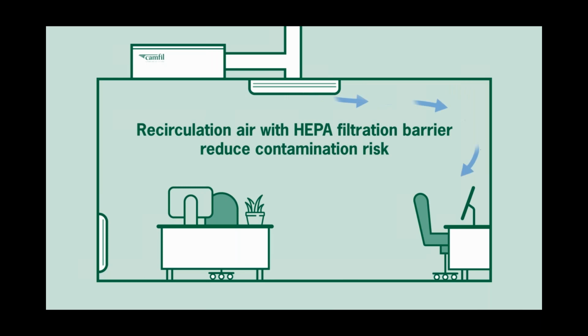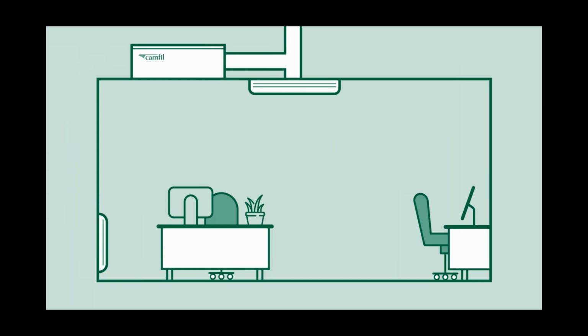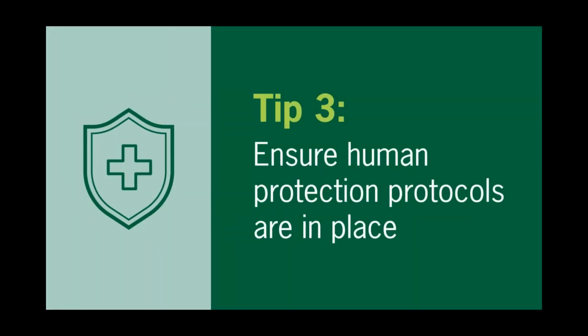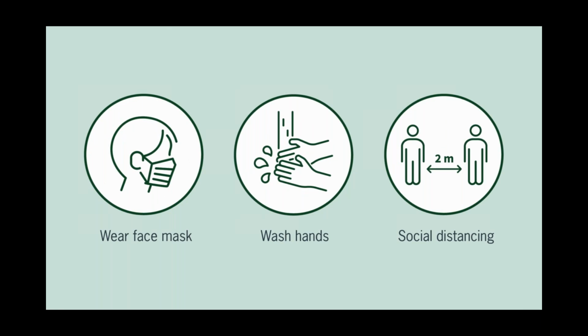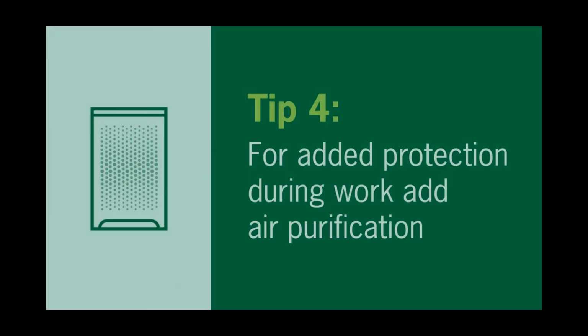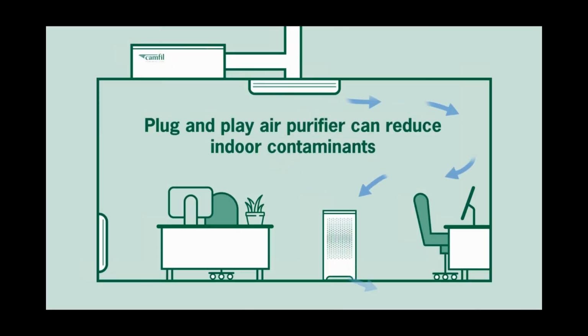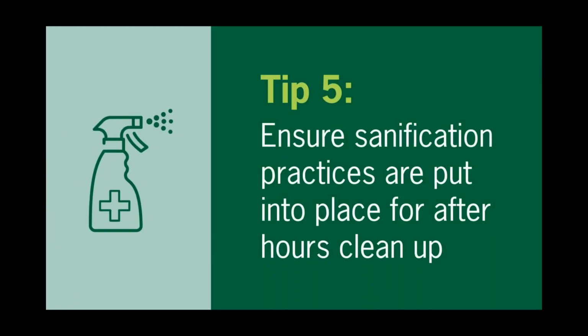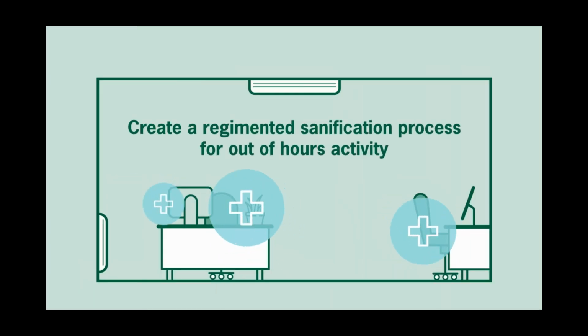And if recirculation is required, try and install a HEPA barrier somewhere. Whether that's up in the ductwork, that might mean adjusting some ductwork or adding an air cleaner in the ductwork. It typically might mean adding an air cleaner because the ductwork or the system may not handle the extra pressure. Either way, you still have to ensure that all of the human protection protocols are in place. And then they're saying that for added protection, look at air cleaners, plug and play. Can you fit an air cleaner into the indoor environment? It's a standalone system. It's going to work in conjunction with your ventilation system, but it's a standalone system. And always ensure that sanitation practices are put in place during and after out of hours activities.